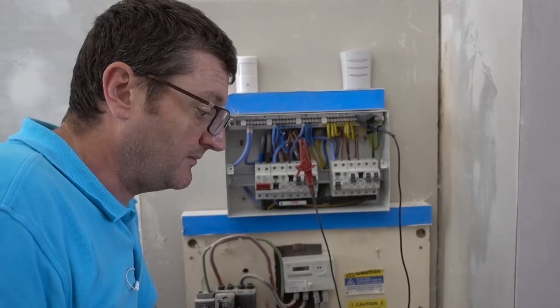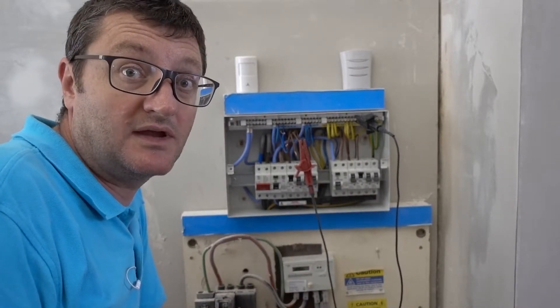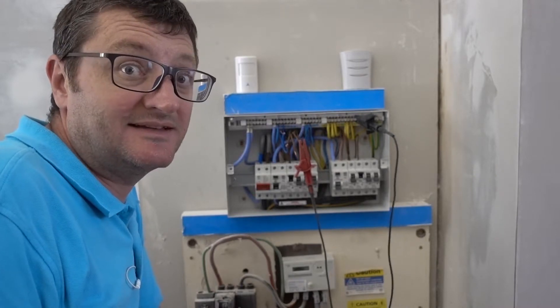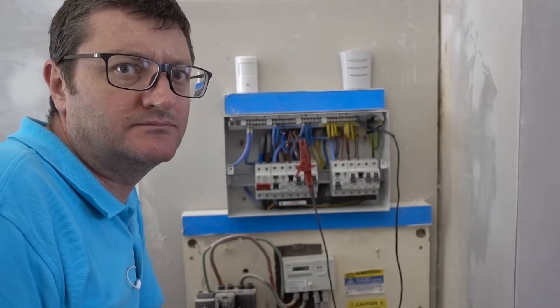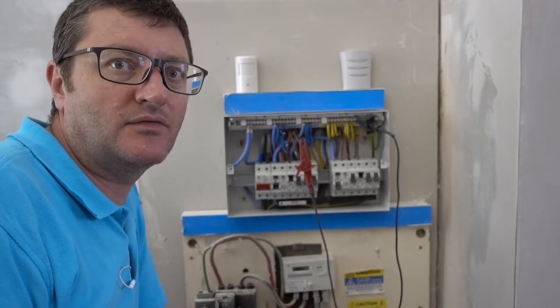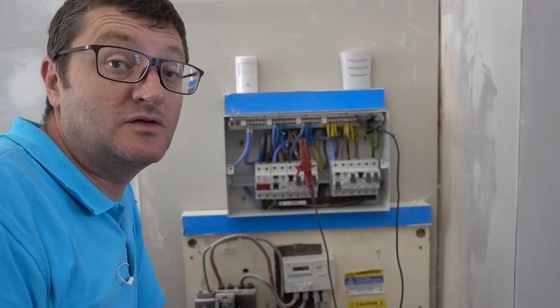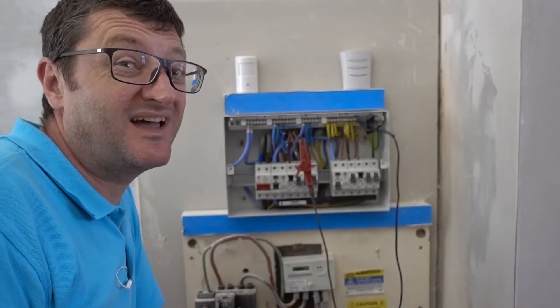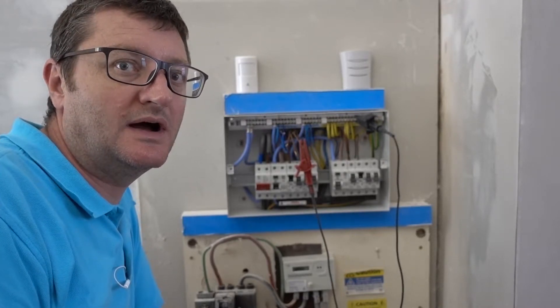It's anything over 1 mega ohm, according to the regs, is okay. Once you're getting a single figure, you want to be starting to wonder what might be wrong with your circuit. I had that nail through wire brought me down to 2 mega ohms, which the regs actually say is okay. But I wasn't happy with that. So I wanted to change the wire.